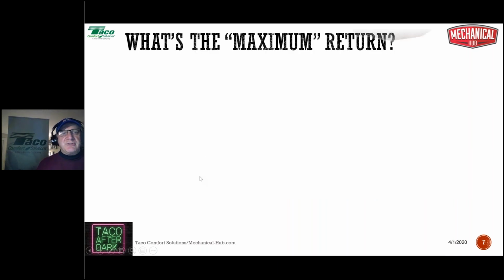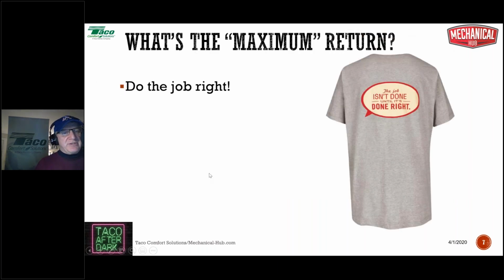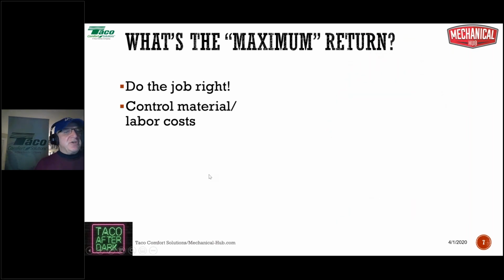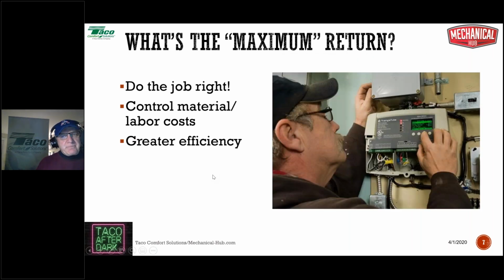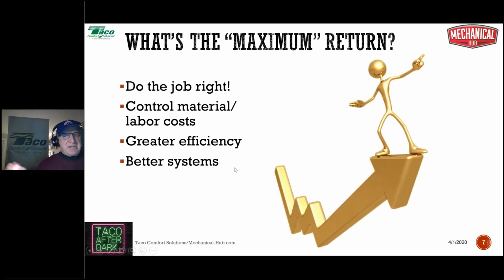The maximum return, well, it should be obvious. There's that intangible of knowing that the job's been done right, and you can pat yourself on the back for that. But there are some tangibles. You can control your material and labor costs, as we discussed. You deliver a system that has the efficiency as advertised, not just combustion efficiency, but true system efficiency. If everything is sized properly, you're not over-pumping to a terrible degree, the pipe is sized properly, the boiler is sized properly, you have greater system efficiency, and that should lead to better systems and the rewards that follow. So that's the maximum return.